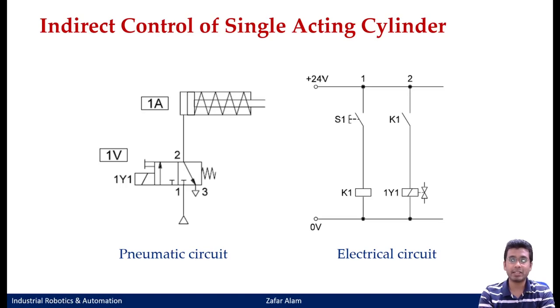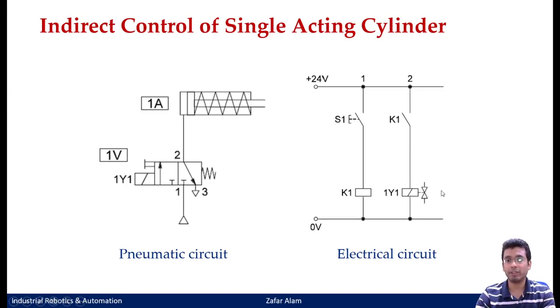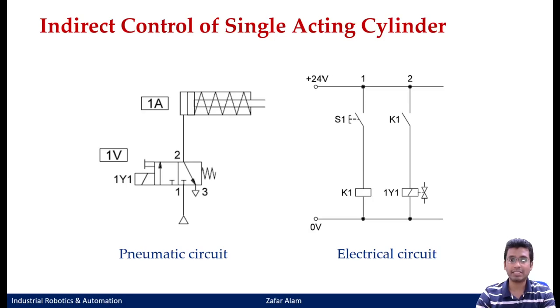However, when you go for indirect control of a single acting cylinder, note that there are no changes to your pneumatic circuit — whatever change exists is in the electrical portion. For an indirect control, we are using a relay, and through that relay we are energizing our solenoid valve 1Y1. Using a push button, we energize this relay and we use a make contact of the same relay K1 to energize our solenoid valve. This is known as your indirect control of a single acting cylinder.